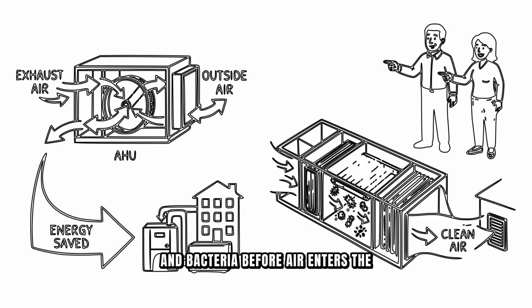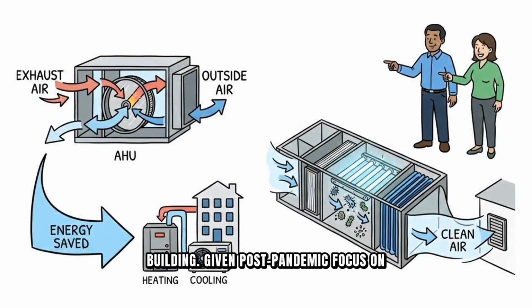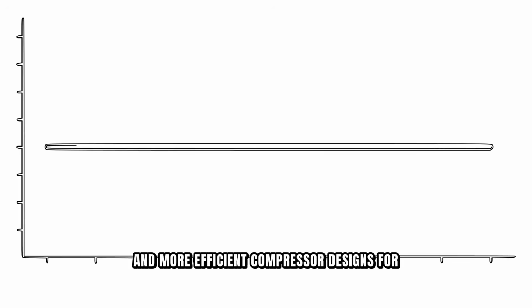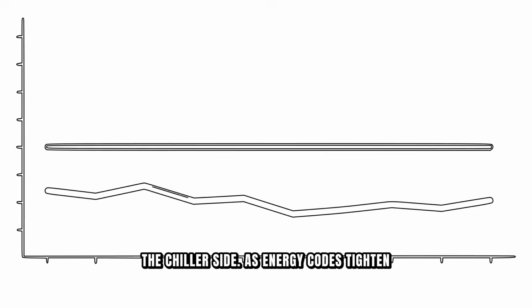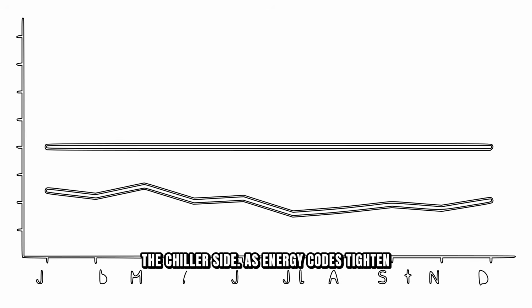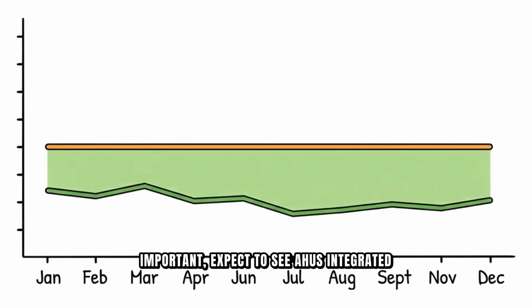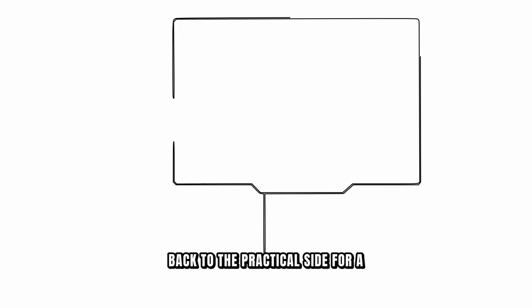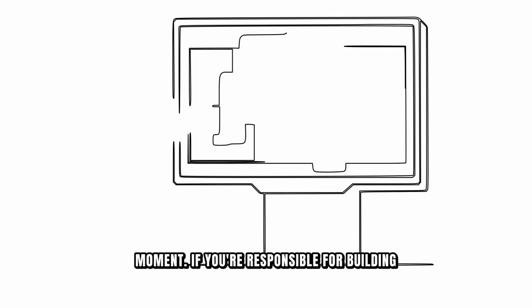Another emerging technology is ultraviolet light in the AHU to kill mold spores and bacteria before air enters the building. Given post-pandemic focus on indoor air quality, UVC systems are becoming more common in new installations and retrofits. Some manufacturers are also experimenting with natural refrigerants and more efficient compressor designs for the chiller side. As energy codes tighten and carbon footprints become more important, expect to see AHUs integrated more tightly with renewable energy systems, thermal storage, and smart building networks.